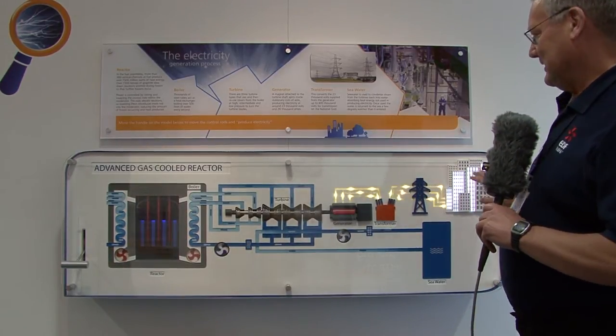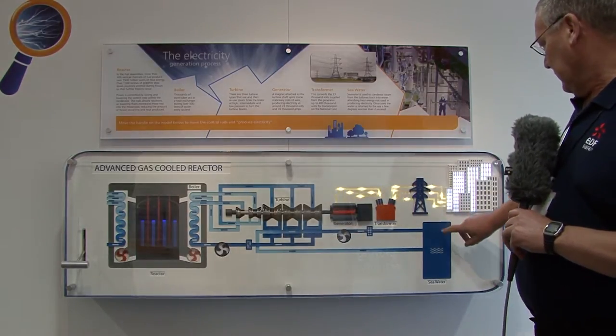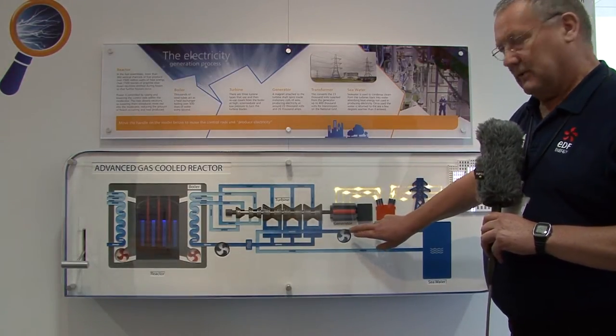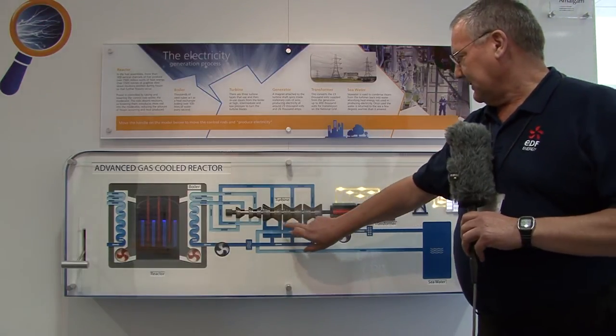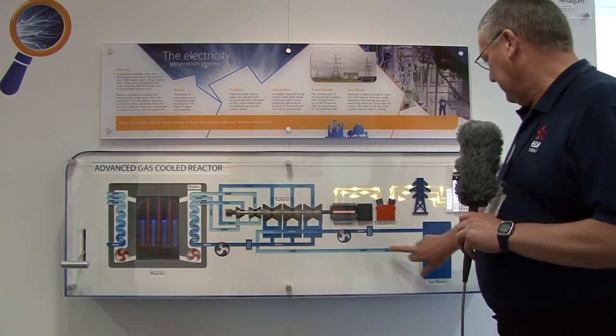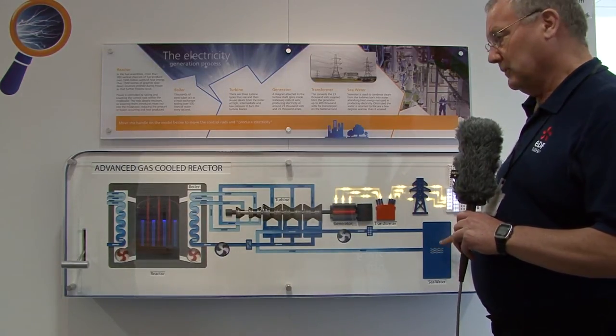This is a diagram of Torness Power Station. On the CW side, the cooling water is brought in from the sea through drum screen filters. It then goes through four main CW pumps, which send the seawater up to the condenser in the turbine area, and then it returns back to the sea on the far side of the station at the cooling water outfall.